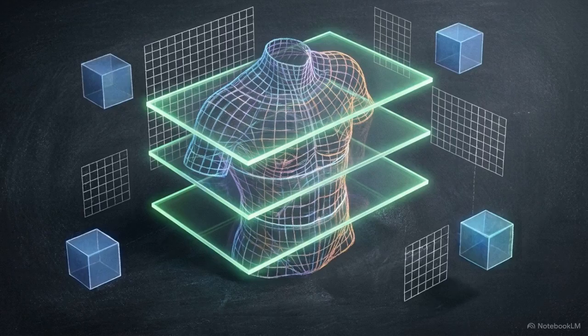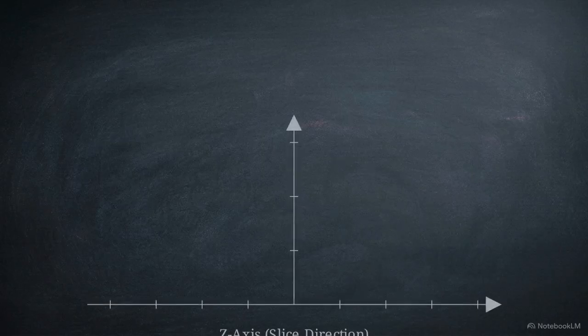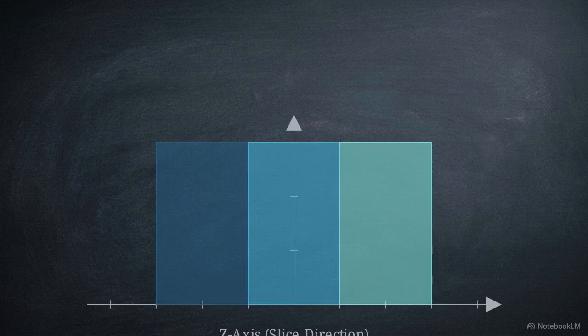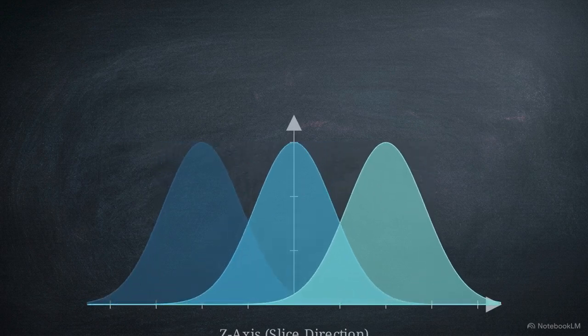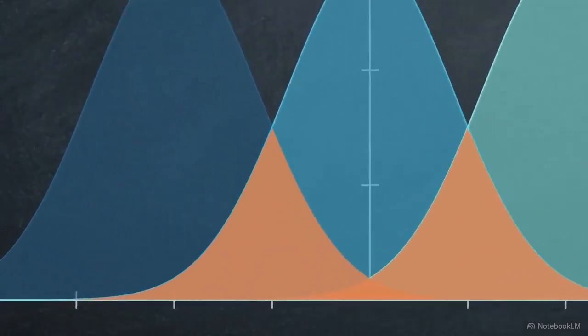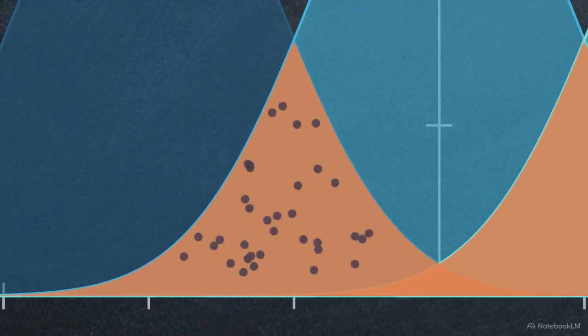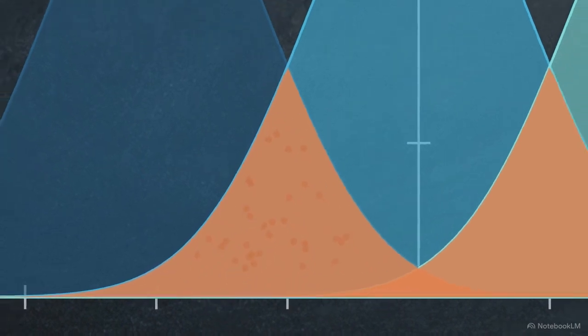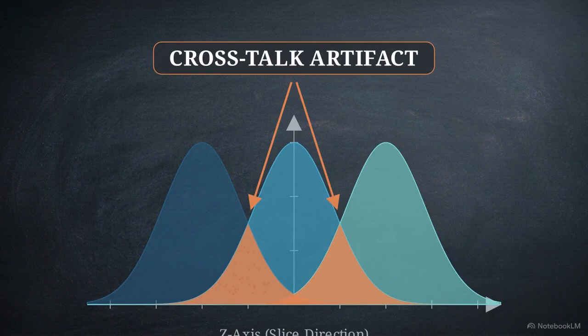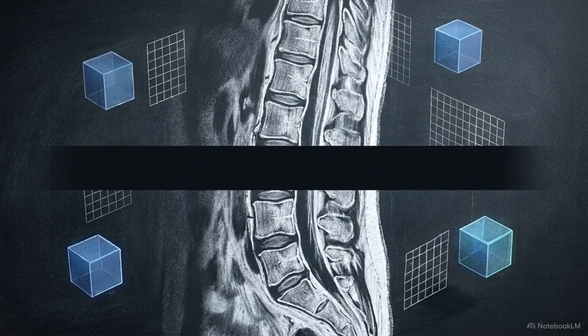Beyond the internal dimensions of a single voxel, we must account for the macro interaction of multiple adjacent slices in a scanning sequence. Theoretical equations treat slice boundaries as perfect rectangles. Physical radiofrequency pulses, however, produce an excitation profile shaped like a Gaussian bell curve. Because these curves slope outward, their edges inevitably overlap with adjacent slices inside the patient. Protons in these overlapping boundary zones are prematurely excited and saturated by adjacent pulses. This creates an artifact called crosstalk. When the scanner finally attempts to read a specific slice, those previously saturated protons yield zero usable signal, destroying the image contrast in that region.